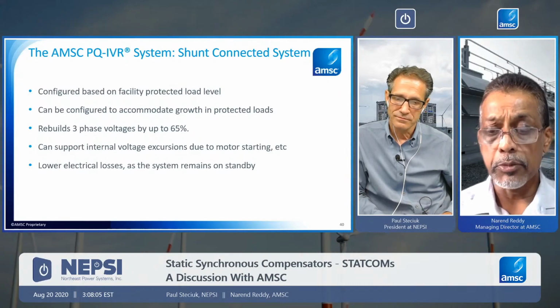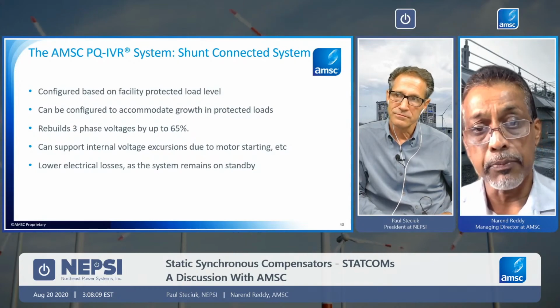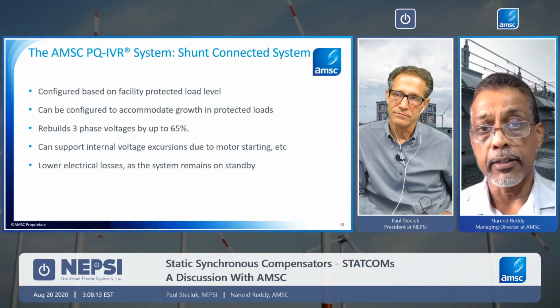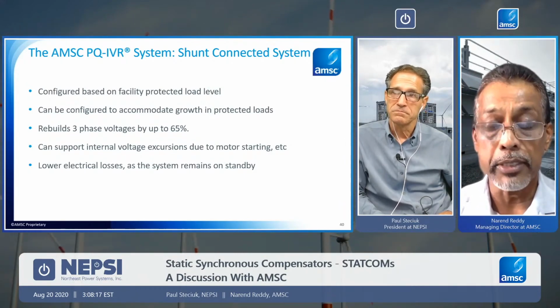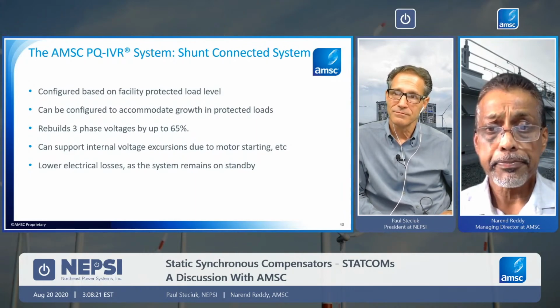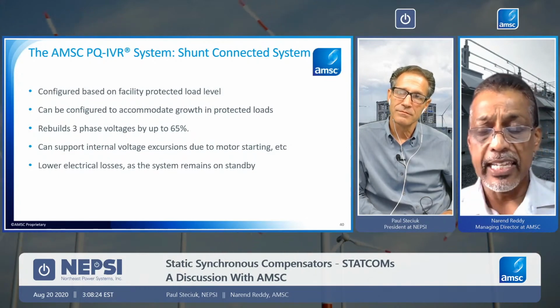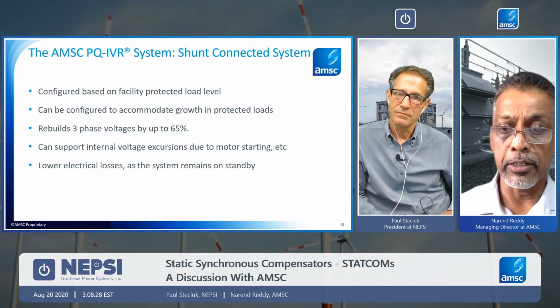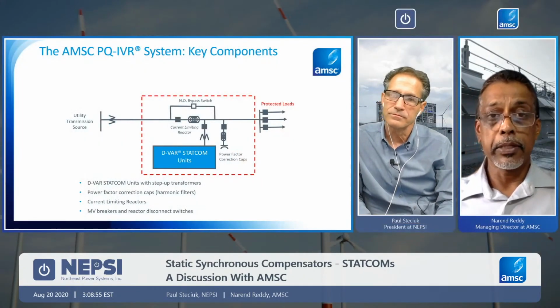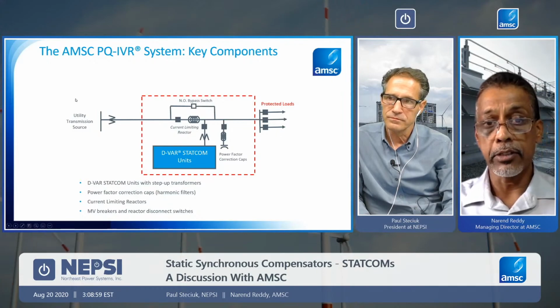So there's a fair bit of work that goes into this, but in essence, what we do is design systems to provide rebuild of voltage, for example, in this case, voltages down to 30%, rebuilt up by 65%, so bringing them up to normal operating level. We also make sure that the system overall is managing all of the operations downstream of this installation, meaning that whatever customers' large facilities, motors, and things like that are operating, they're not impacted. And also, a key thing is that the system remains on standby, so we want to make sure that there are low electrical losses, with the system doing nothing and only waiting for a sag.